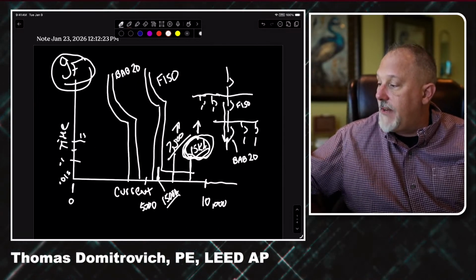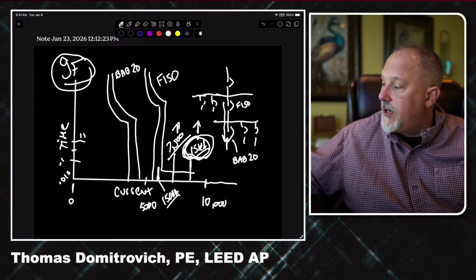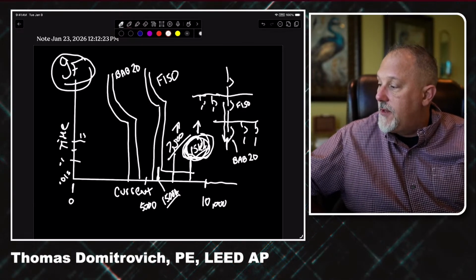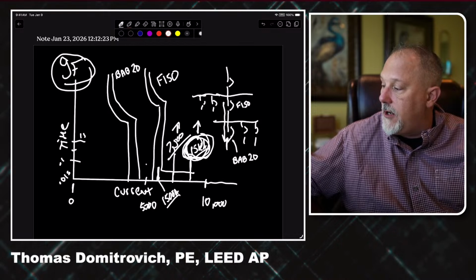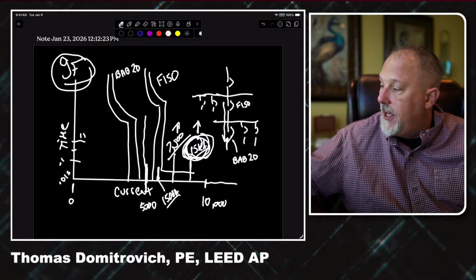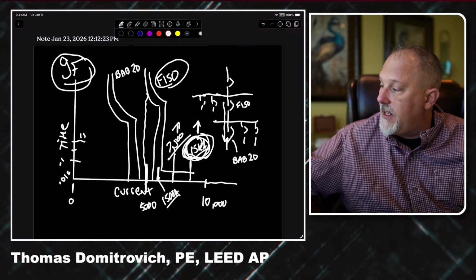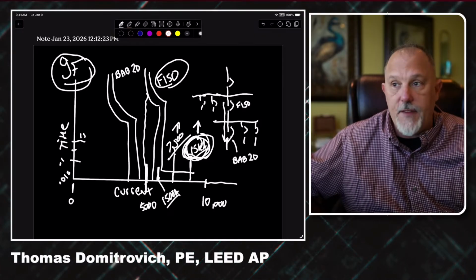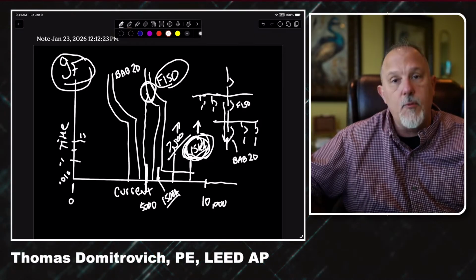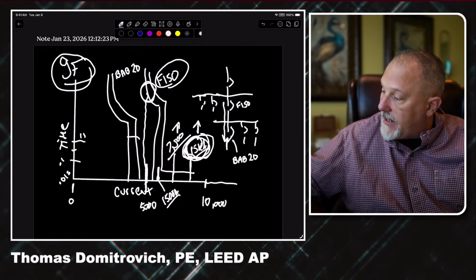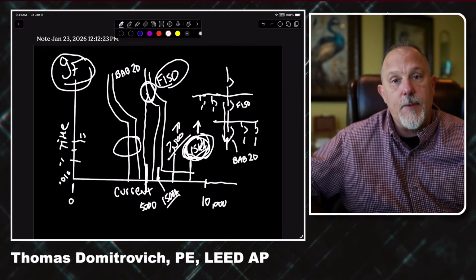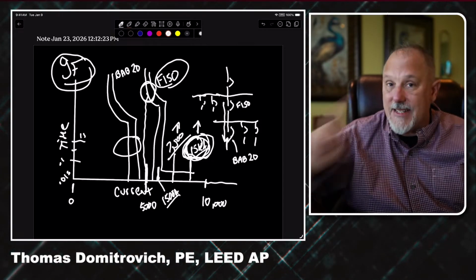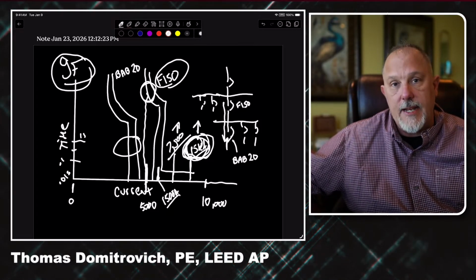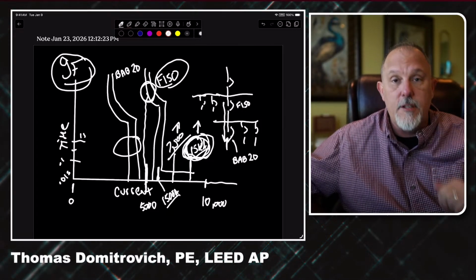Okay? So these devices will respond, but you're not going to see the 15,000 amps. Let's say that the ground fault currents are really low and it's going to be somewhere in this range. That F150 is, if it's greater than 150 amps, it's going to respond somewhere up in that time period. It's going to give that downstream breaker enough time to react because that single pole, you're already in the instantaneous region for a single pole device.